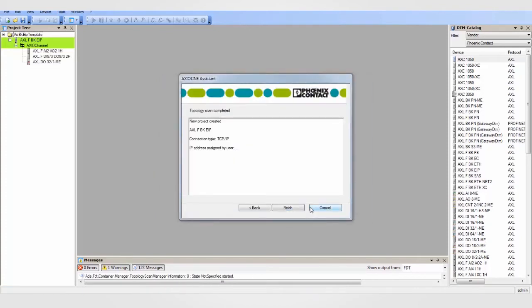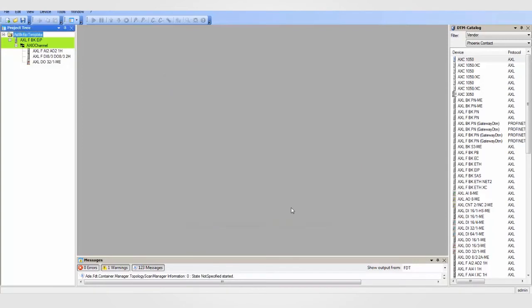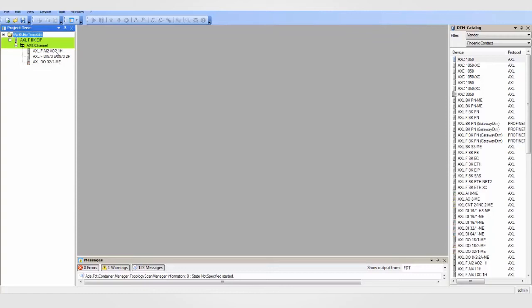Once finished, you will see the connected I.O. listed on the left-hand side of the screen. In this example, you see three I.O. modules. The first module is a combination analog input-output module that needs to configure the channels for voltage or current ranges. The last two are digital I.O. and don't require a specific configuration unless you want to set location information or fault response modes.